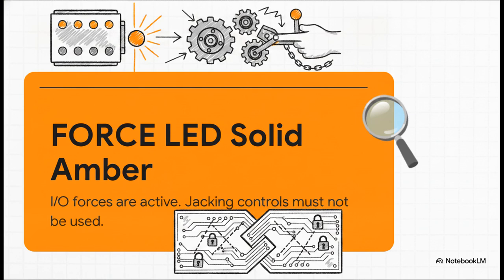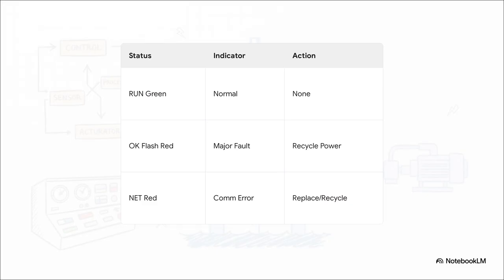If you see this, you absolutely must not touch the jacking controls. Initiating a sequence with forced I/O can lead to catastrophic, completely unpredictable rig movements. You literally have to wait until a qualified programmer accesses the logic and removes those forces. For day-to-day operations, the indicators are pretty straightforward. A solid green run light means you're good to go. Now, a solid red OK light during the initial power-up is normal. That's just the controller loading its project into memory.